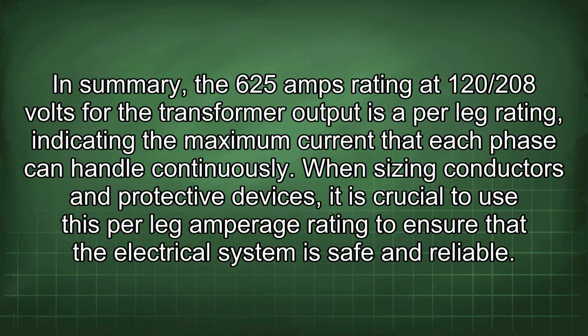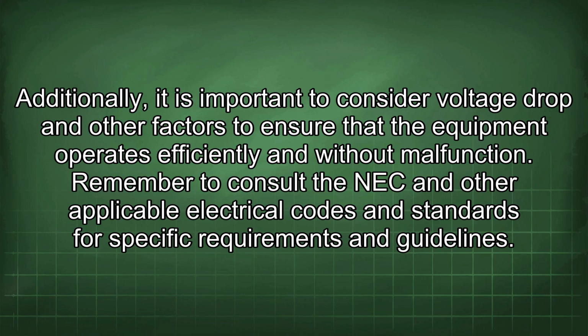In summary, the 625 amps rating at 120/208 volts for the transformer output is a per leg rating, indicating the maximum current that each phase can handle continuously. When sizing conductors and protective devices, it is crucial to use this per leg amperage rating to ensure that the electrical system is safe and reliable. Additionally, it is important to consider voltage drop and other factors to ensure that the equipment operates efficiently and without malfunction. Remember to consult the NEC and other applicable electrical codes and standards for specific requirements and guidelines.